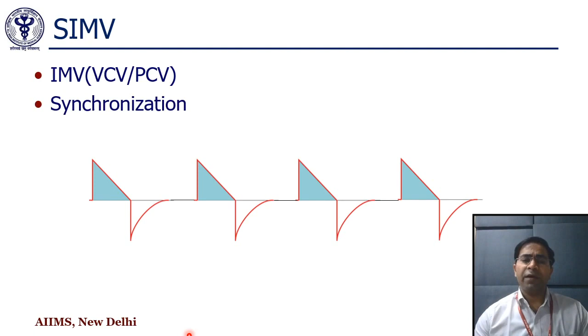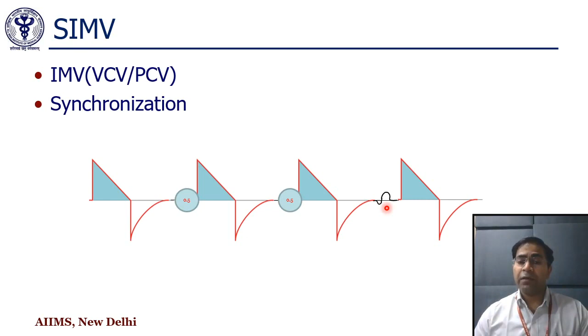That means if we set the respiratory rate at 10, then each cycle is 6 seconds, or after every 6 seconds the patient is getting one inspiration. So within 0.5 seconds of that 6 seconds, that means from 5.5 to 6 seconds, if a patient is trying to breathe, then the machine will synchronize with that breath. This is known as SIMV, or synchronized intermittent mandatory ventilation. The beauty of this mode is that the patient can breathe in between the breaths on their own. But the patient has to breathe against the demand valve. That leads to an increase in the work of breathing.